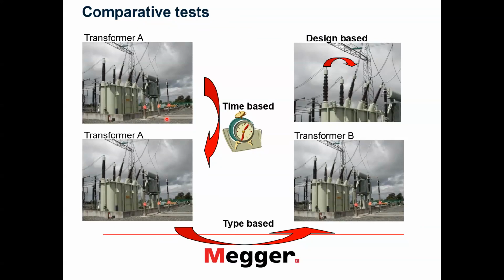If we don't have a reference measurement, but we know that a very similar transformer of the same design is in good shape, we can take that transformer and compare it to the transformer which we measure today. But we have to make sure that the designs are the same and we can really compare, because if these are different types of transformers, there is no point in comparing whatsoever.